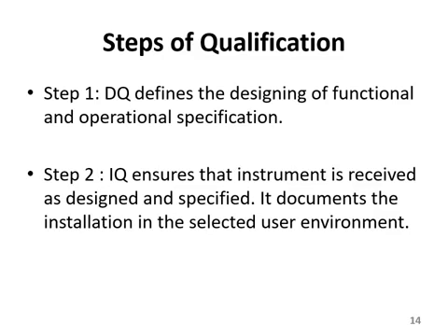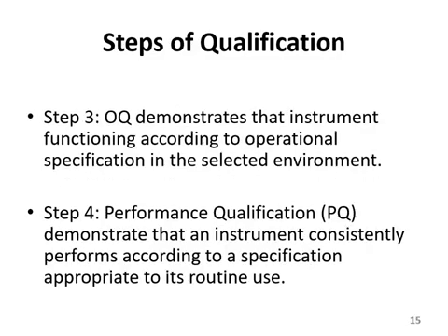Step 3, operational qualification. Okay, it demonstrates that a balance or instrument will function according to its operational specification in the selected environment. We have discussed it. Step 4, performance qualification, PQ, demonstrates that an instrument is consistently performing according to a specification appropriate to its routine use.